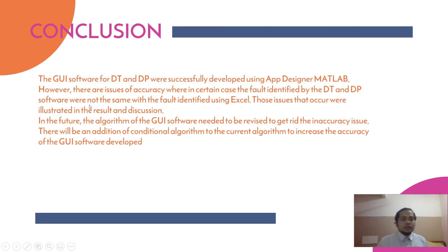In conclusion, the GUI software for DUVAL pentagon and DUVAL triangle was successfully developed using App Designer MATLAB. However, there are issues of accuracy where, in certain cases, as I stated before, the fault identified by the DT and DP software was not the same as the fault identified using Excel. Those issues were illustrated in the results and discussion previously.